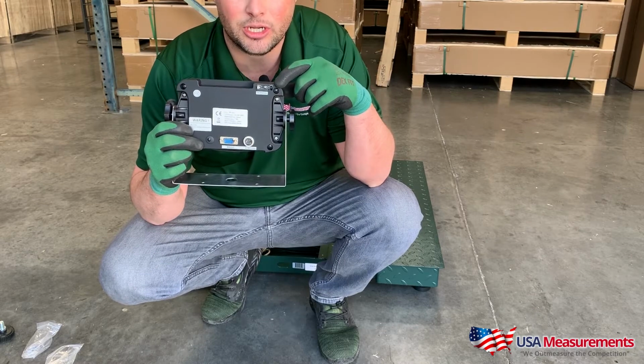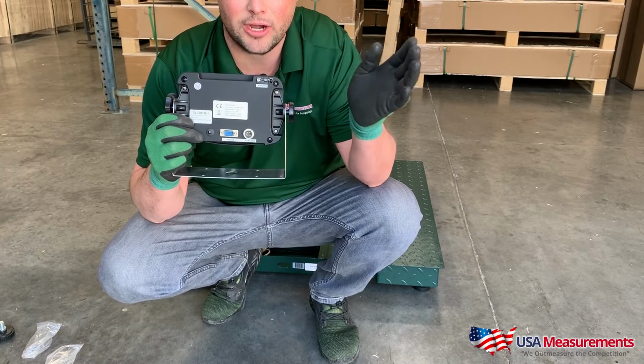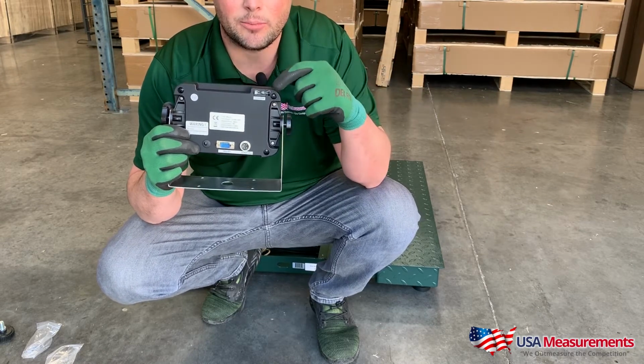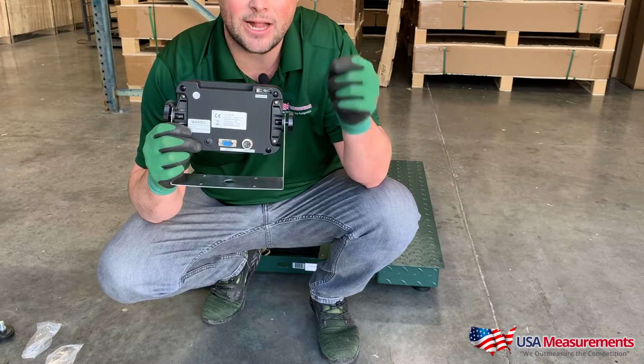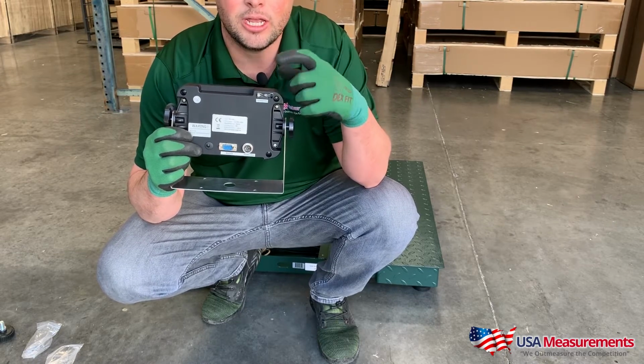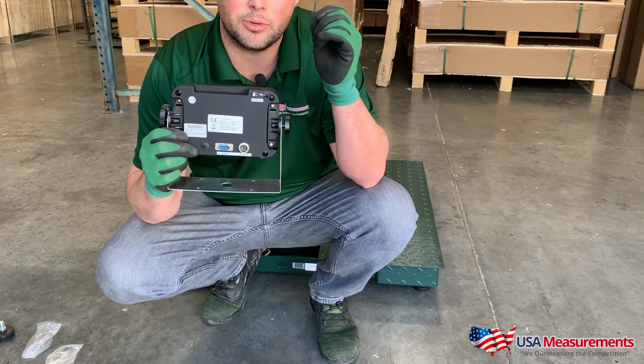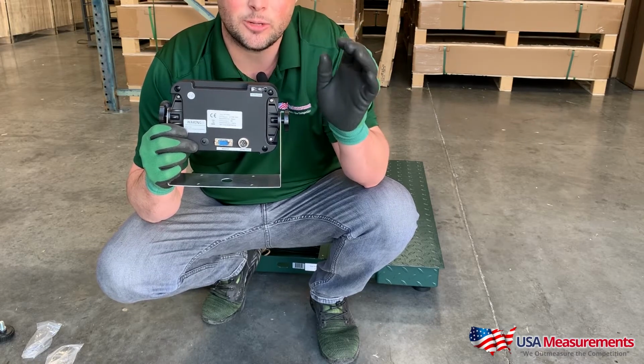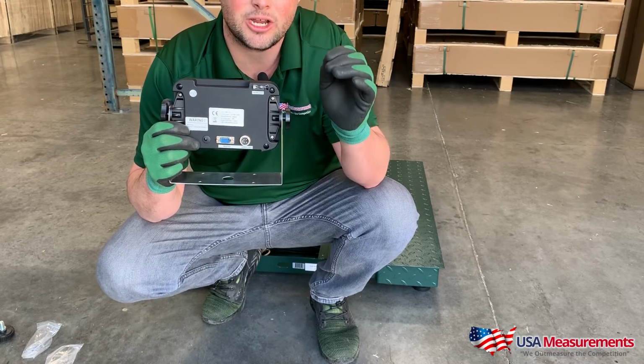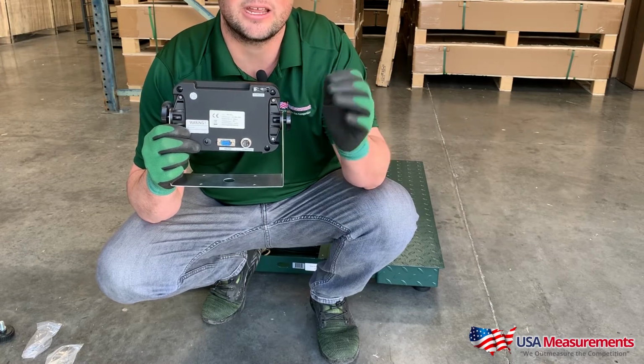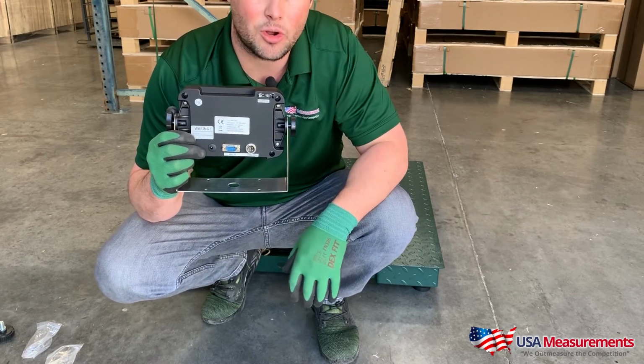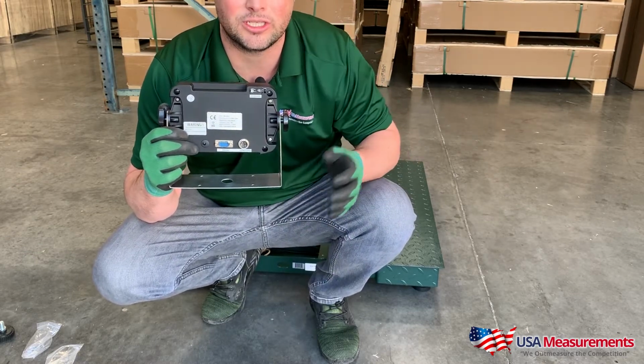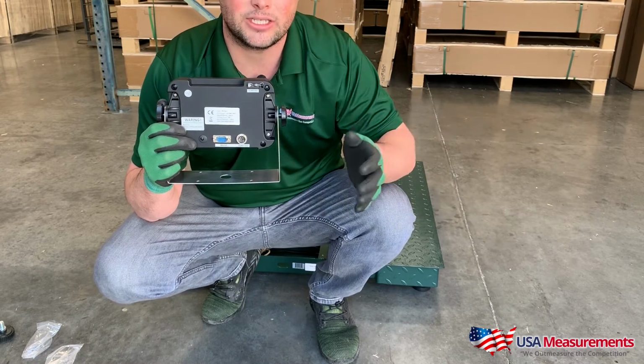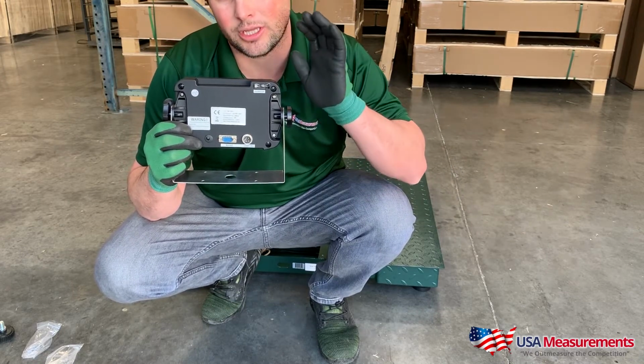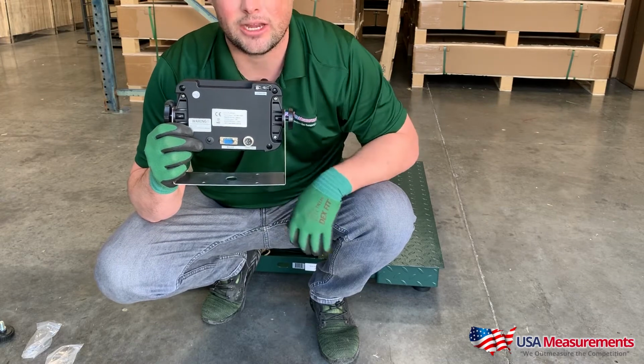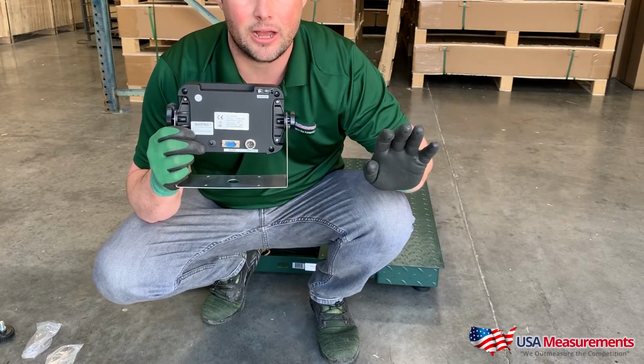Here's something extra we do differently than a lot of our competitors: we put a lead seal here because we calibrate all of our scales prior to shipping to our customers. We put this here because the only way to recalibrate the scale is to break this seal and push the internal button to put it into calibration mode. This helps prevent any customer or user from accidentally putting it into calibration mode and having to go through the whole sequence to recalibrate. We do this so our customers know the scale is coming calibrated and won't have any issues setting up on arrival.